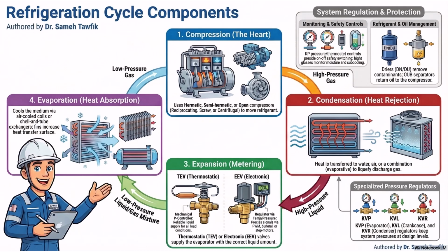That's a perfect visualization. And that actually brings us to the crucial turning point in the cycle. Because we've pressurized the gas and dumped the heat. Right, turning the refrigerant into a high-pressure liquid. But if we want to actually cool the air in our cargo hold, we need to transition from the high-pressure side of the system to the low-pressure side. We need to let that liquid expand. Exactly. Here's where it gets really interesting.